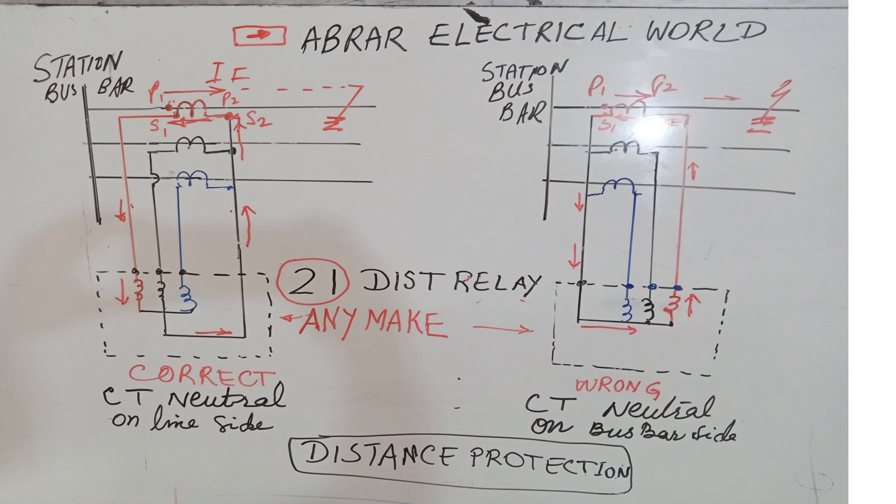I have made a video on CT polarity and will make another one. Now, if the fault current flows in this direction, the CT current will be in the opposite direction due to Lenz's law. If this terminal is dotted and this is also dotted — this is P1 and this is S1 — then current entering the primary will come out from secondary S1, the dotted point, and go into the relay, then return to the neutral. This is a distance relay.